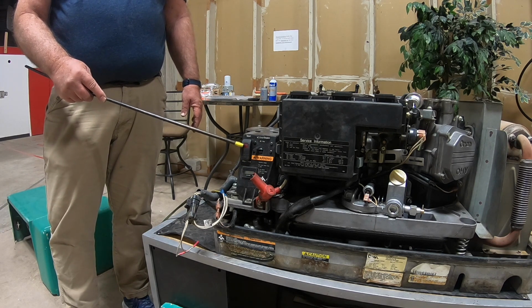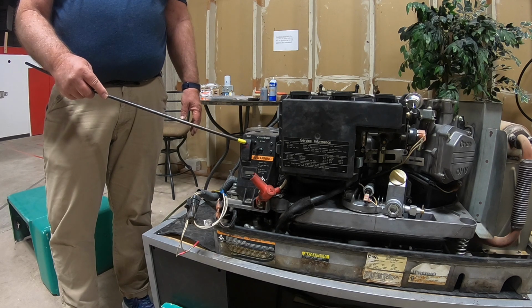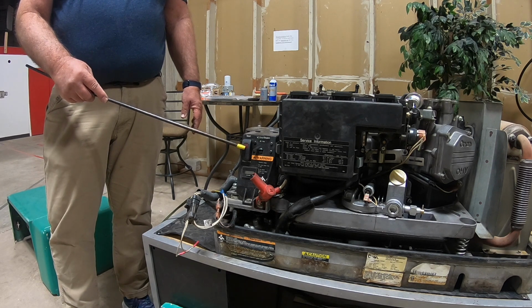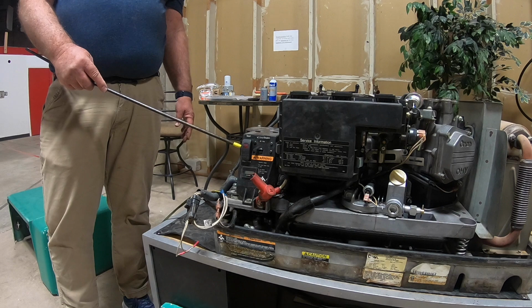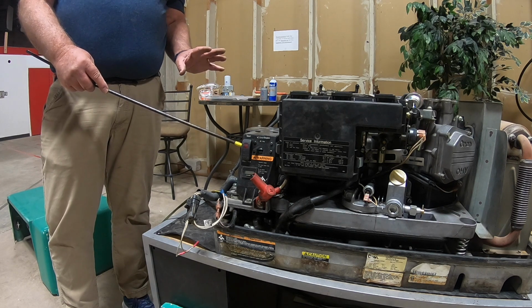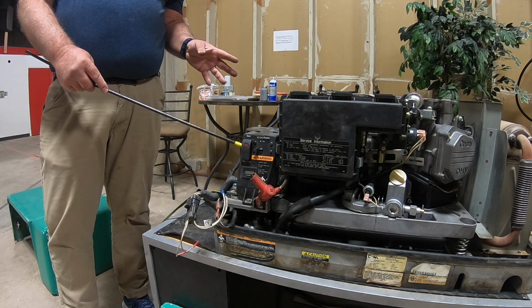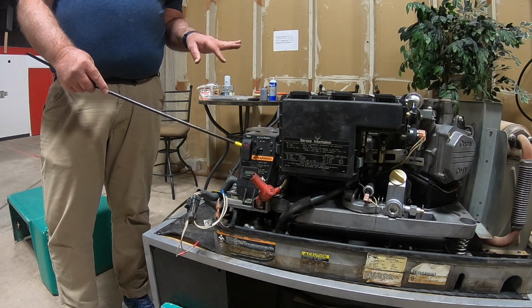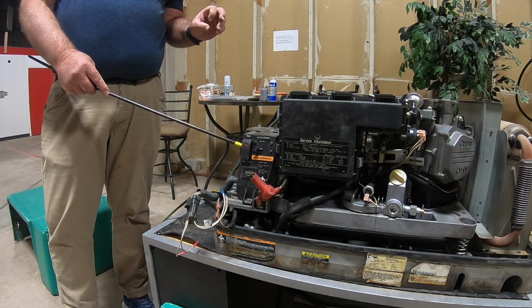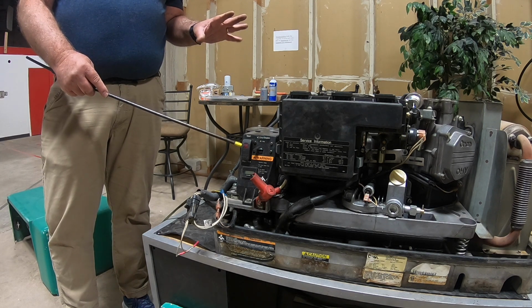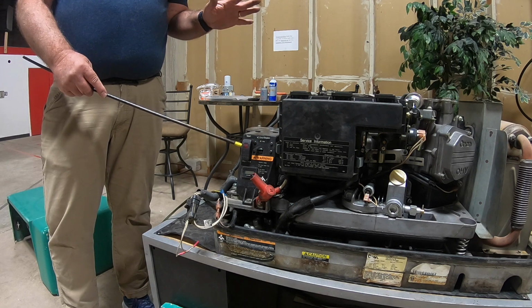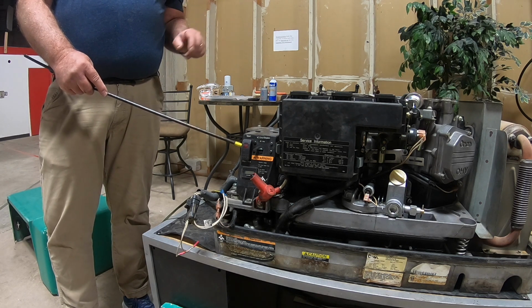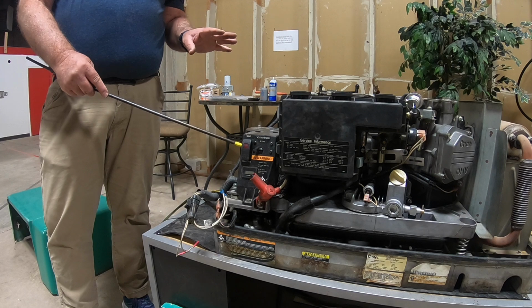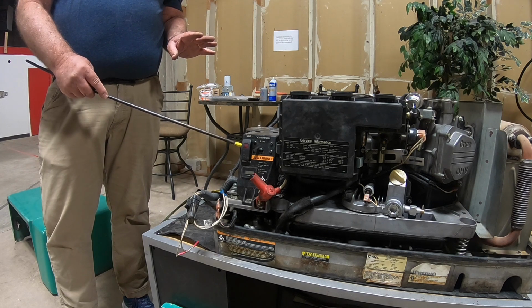Also, right here on your remote start/stop on the generator, there's a red square in the middle. If the unit is displaying problems, the lights will flash there. There are two sequences: first it'll flash 1 through 3, then pause, then go between 1 and 5, maybe even 6. That gives you the trouble code, and when you go back and look in the manual, it'll give you an idea of where to look for your problem.